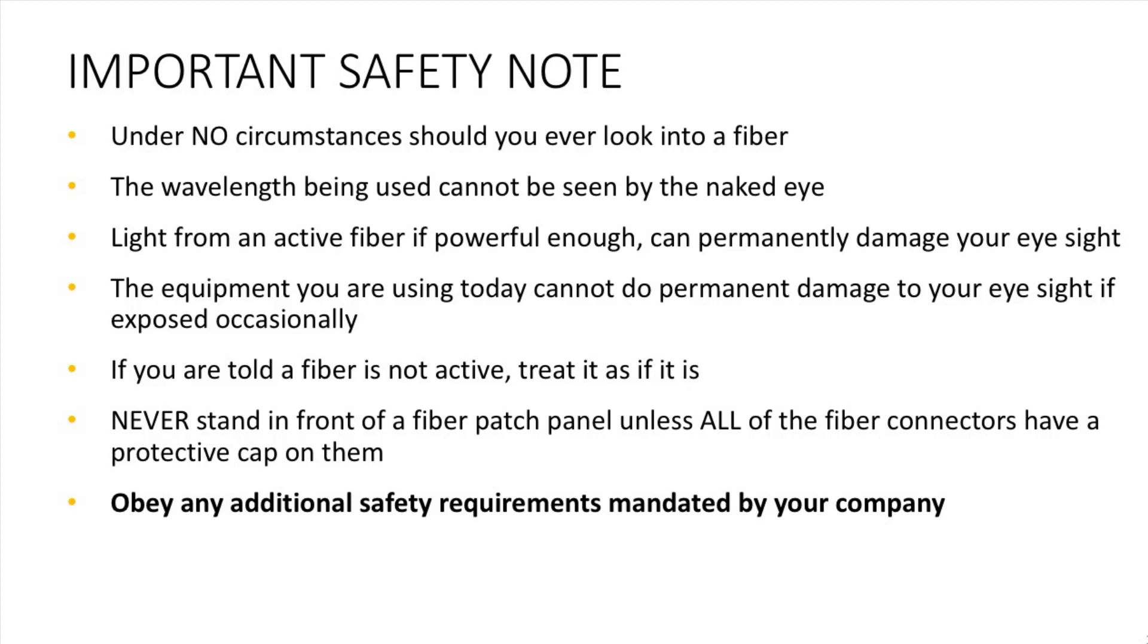The equipment we are using today cannot do permanent damage to your eyesight if exposed occasionally. If you are told a fiber is not active, treat it as if it is. Never face the front of a fiber patch panel unless all of the fiber connections have protective caps on them. Obey any safety requirements mandated by your company.